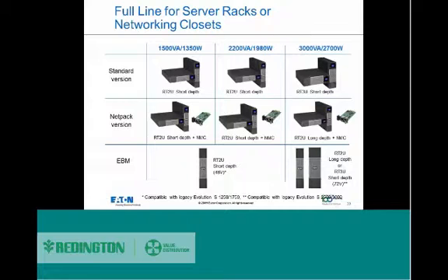Now, another thing to note here is the power factor for each of them. If you look at the real power that the unit can take up, for the 3 kVA, as you can see, it is 2.7. So that's why you have a very high power factor of 0.9.